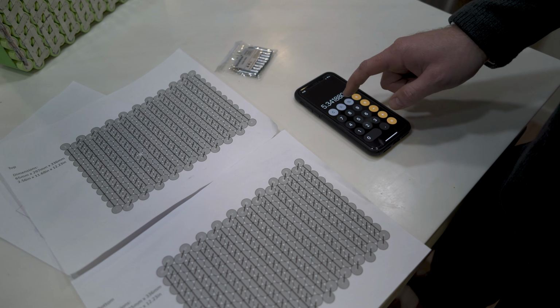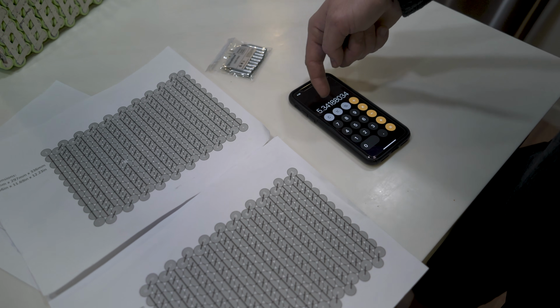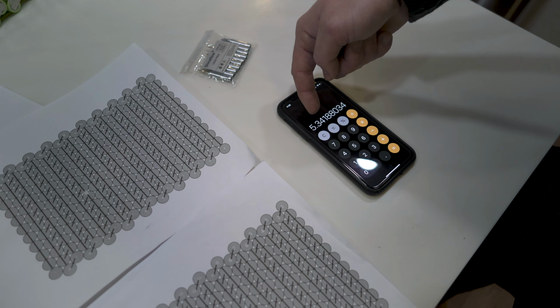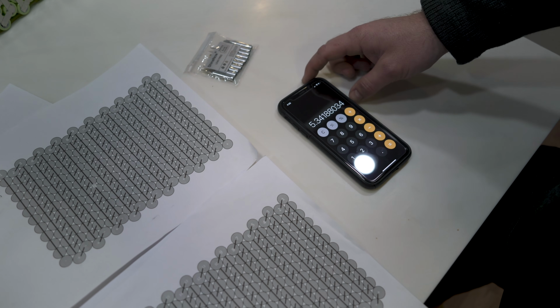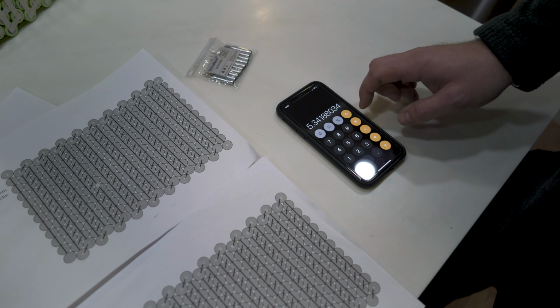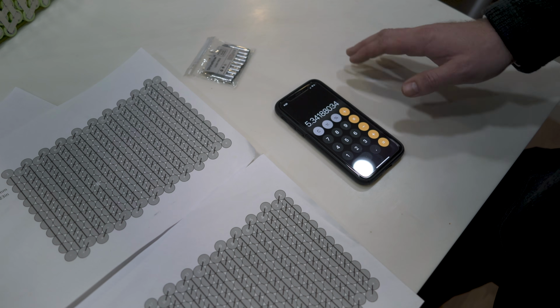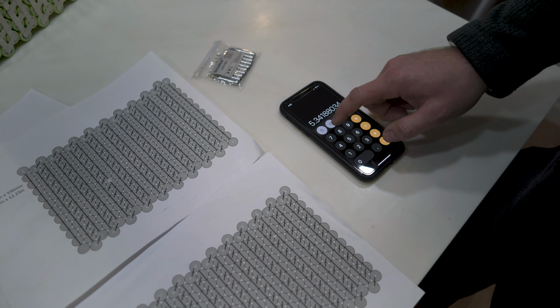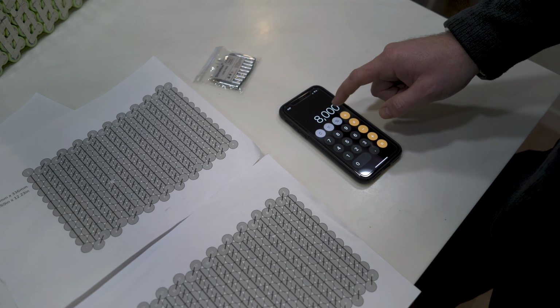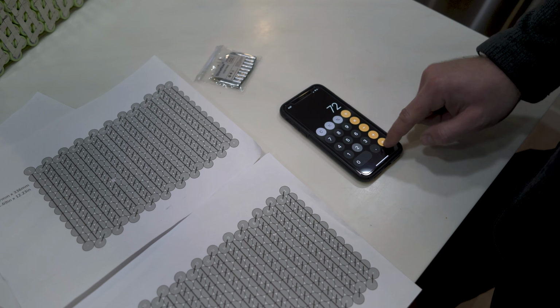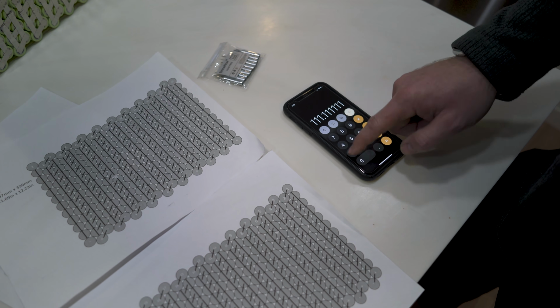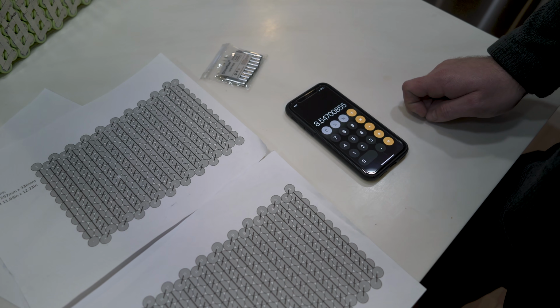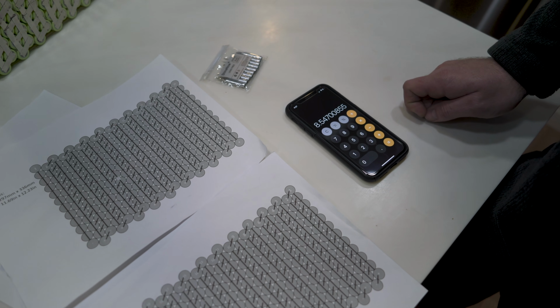If we were to do 5,000 watts, this is fairly well below, less than 2C, which is pretty easy to deliver even for a high capacity cell. Once you get to 8,000 it starts to get a bit uncertain. So divide that by 72 to get the amps, then divide by the 13 cells in parallel. I don't want to subject these to over 2C for a significant period of time.